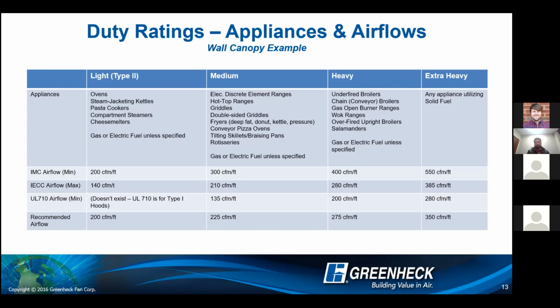Once we've determined the CFM of the hood, you need to make sure that your exhaust ductwork is sized properly. And what Greenheck would recommend is sizing the velocity in your ductwork to be 1,500 feet per minute. So again, the CFM value is CFM per linear foot of hood, and the velocity that needs to be maintained within the duct collar, we would recommend designing to 1,500 feet per minute. In most municipalities across the country, the minimum is now 500 feet per minute. There are still some areas, I'm actually in Chicago today, and Chicago's code still says 1,500 feet per minute, but they allow lower velocities because of variable volume systems.